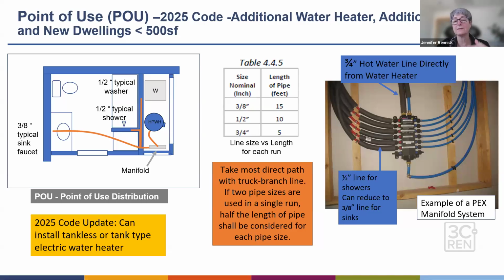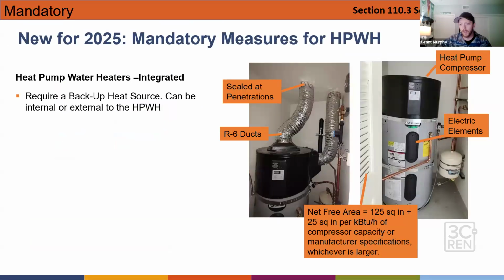And the way we've seen this be met the most with our HERS rater is when they take a direct line from the water heater to a manifold system, and there they can run a straight line to the different fixtures with the smaller diameter pipe. And you want to keep it as compact as possible to meet these requirements. Jennifer, I just want to confirm that includes vertical distance. It's not just horizontal linear. It's horizontal in plan view, but it does clarify that you have to take the most direct path.